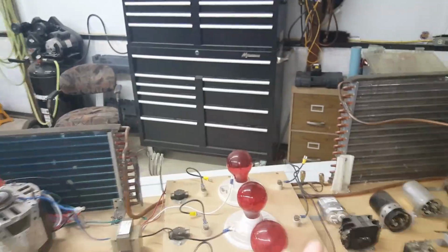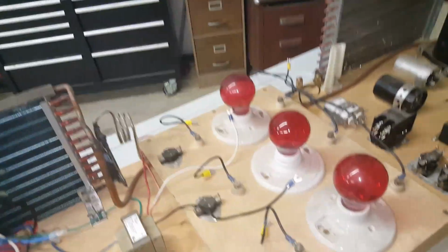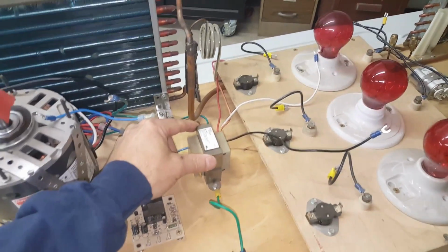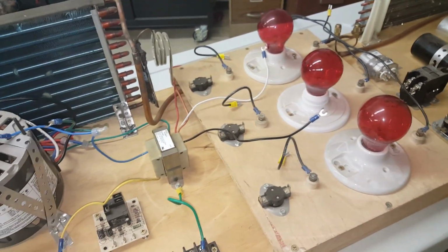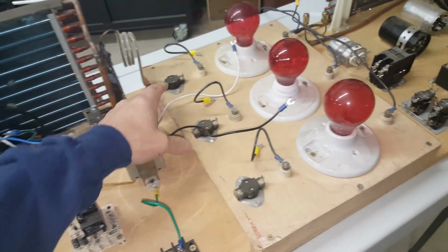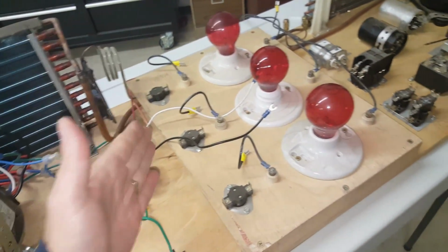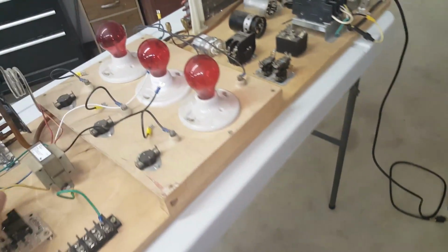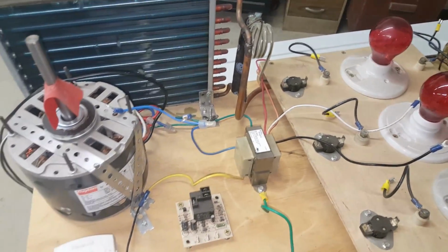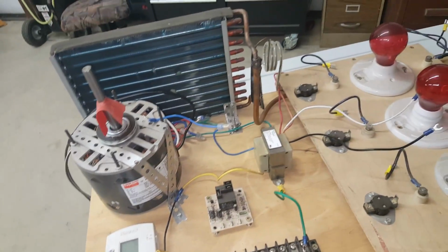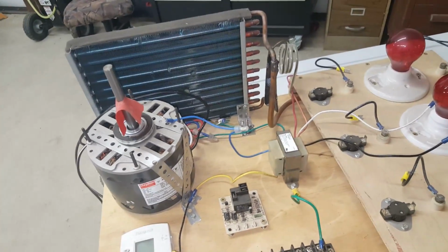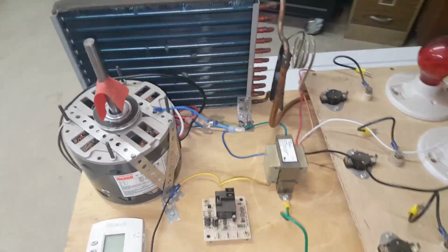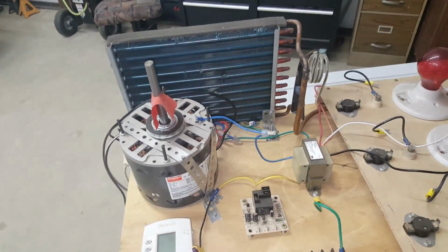I don't want to chase any rabbit at this time, but let me recap on this transformer. It is the 24 volt step down transformer with a 240 volt, 208 or 120 multi-tap on the primary, and we're going to step down to 24 volts to run all of our control voltage. It is rated in VA, and this is a 40 VA transformer. To check how many amps you can pull on the secondary side, you take the 40 VA and divide it by the 24 volt secondary, which will be 1.66 amps maximum.